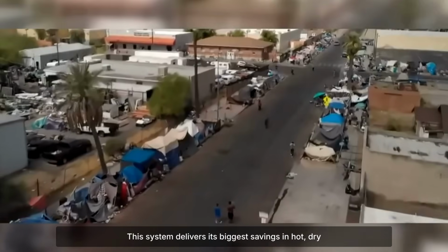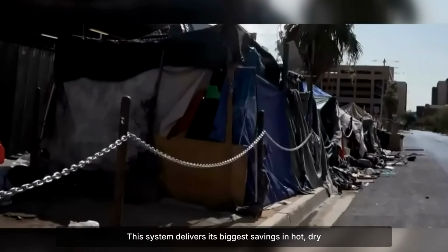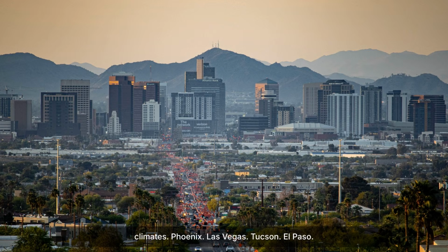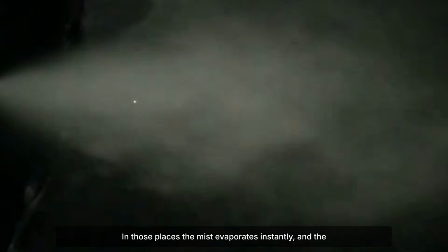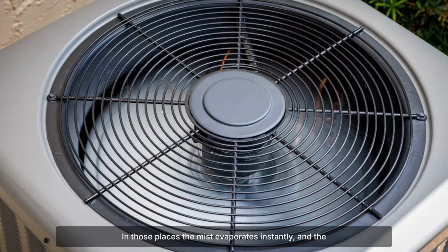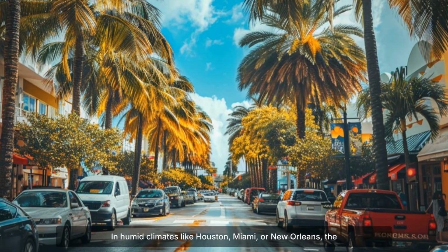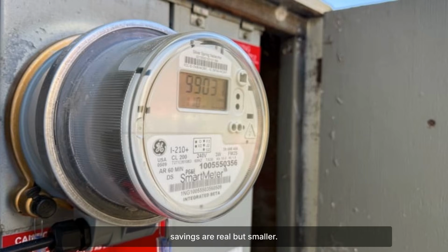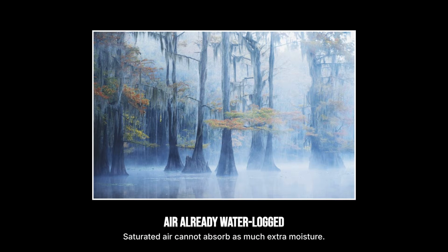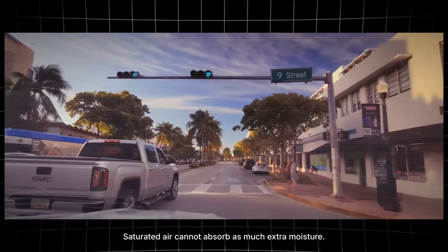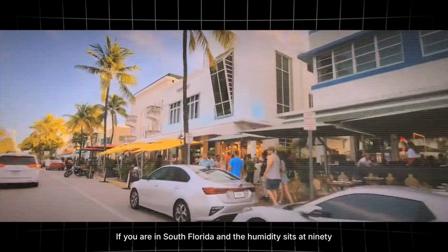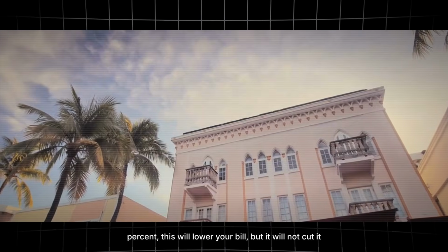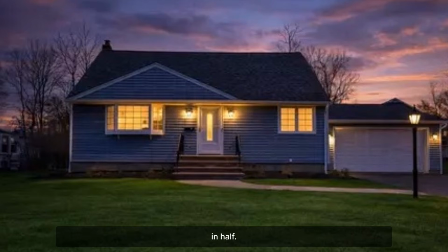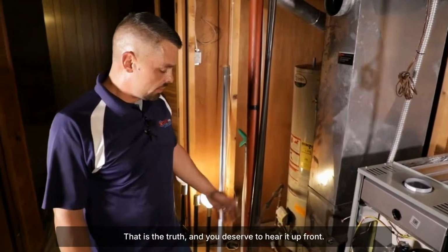Now the honest part: this system delivers its biggest savings in hot, dry climates. Phoenix, Las Vegas, Tucson, El Paso. In those places, the mist evaporates instantly and the temperature drop across the condenser is dramatic. In humid climates like Houston, Miami, or New Orleans, the savings are real but smaller. Saturated air cannot absorb as much extra moisture. If you are in South Florida and the humidity sits at 90%, this will lower your bill, but it will not cut it in half. That is the truth, and you deserve to hear it up front.